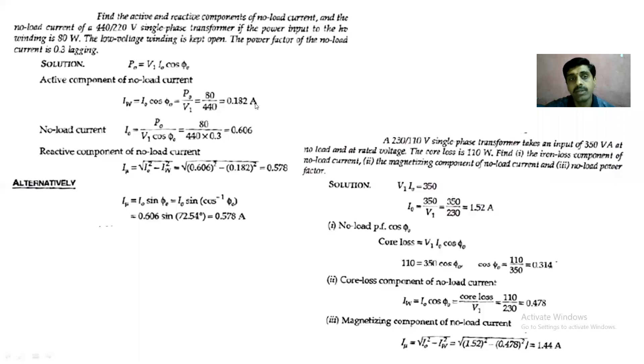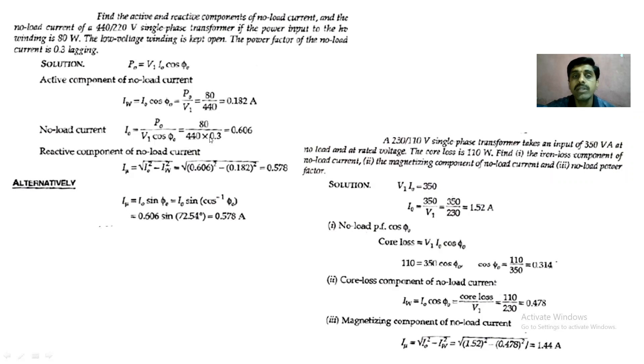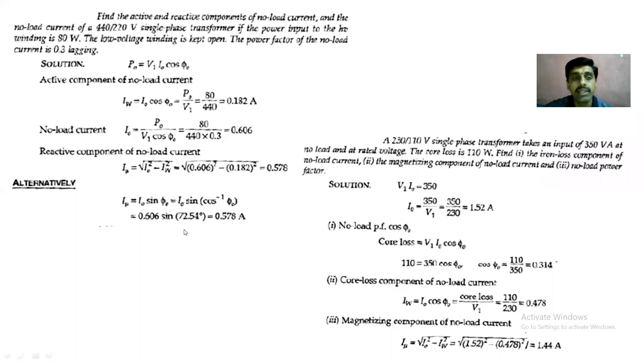After getting IW, we calculate I0 using I0 = P0 / (V1·cosφ0), where cosφ0 = 0.3 and I0 = 0.606 A. The reactive (magnetizing) component Iμ = √(I0² − IW²). Alternatively, Iμ = I0·sinφ0, since cosφ0 is known, sinφ0 can be derived. Either method gives the reactive component of the no-load current.